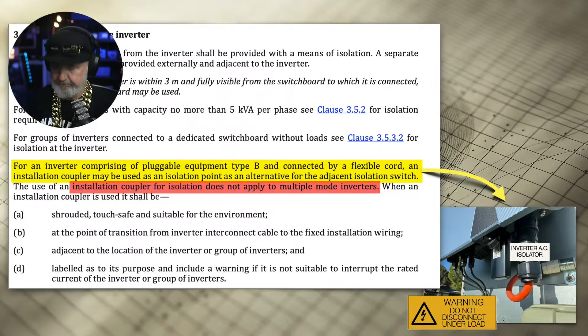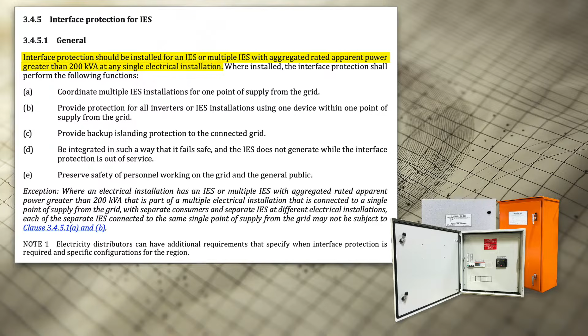Okay, interface protection, as I mentioned before, is now the new term for what used to be called secondary protection, or commonly referred to as grid protection or GPUs, grid protection unit. Those are often quite expensive, whereas now the standard is saying you only require it for systems over 200 kVA. But you will no doubt have to convince your lines company in New Zealand that they will be happy with this, because it will depend on the strength of the grid in your area, whether that's going to be approved or not.